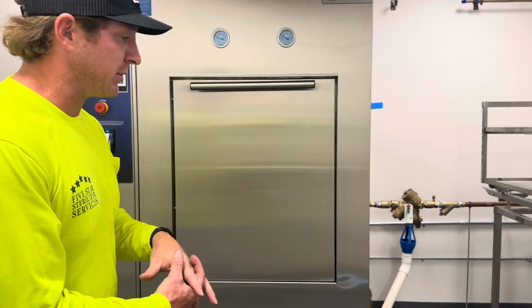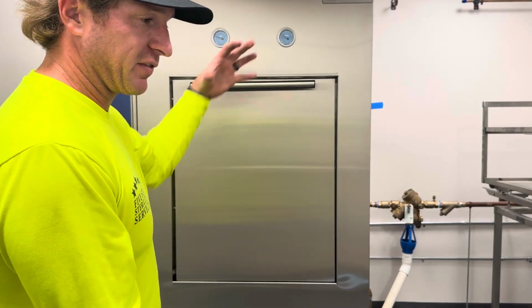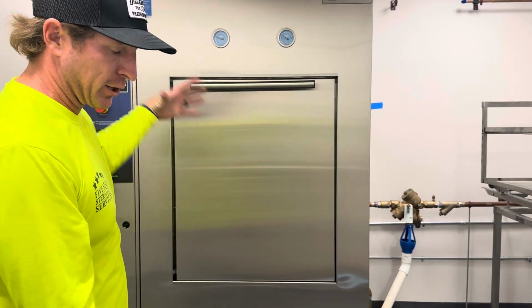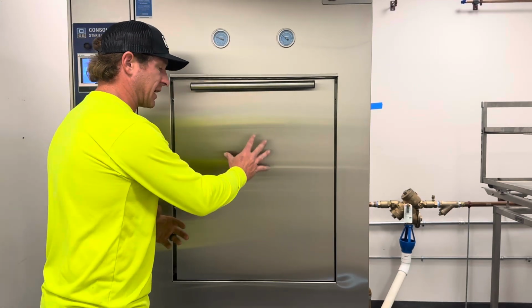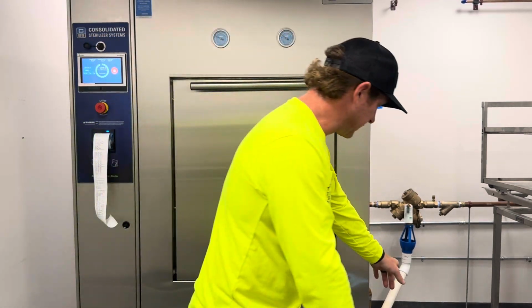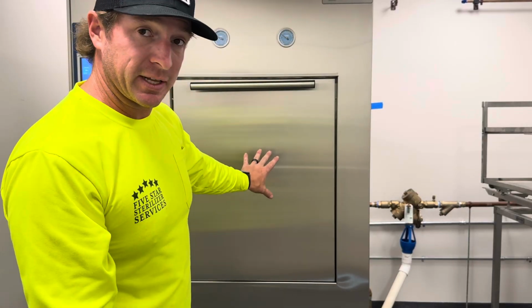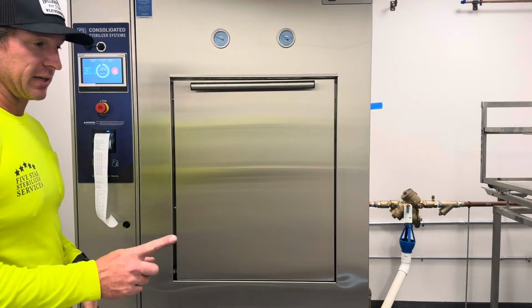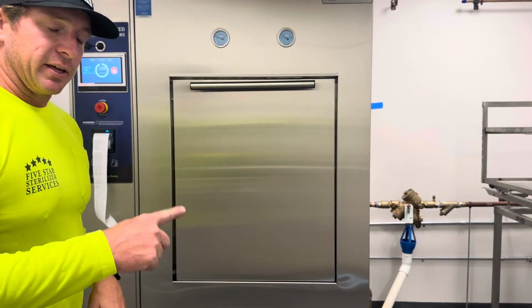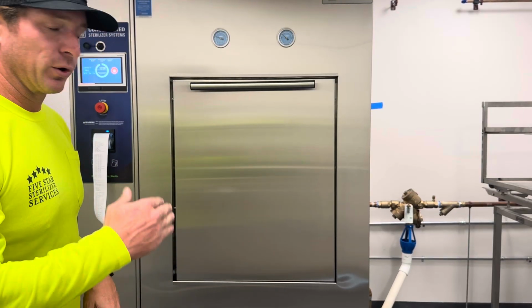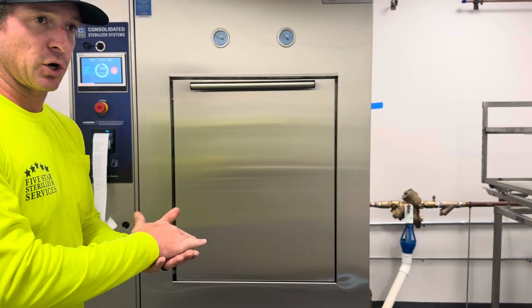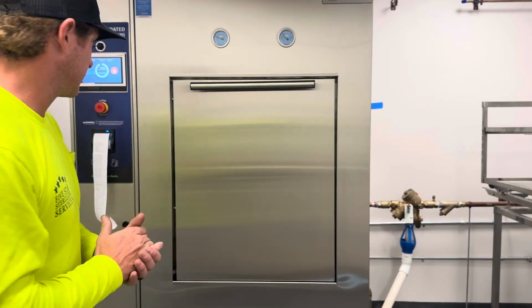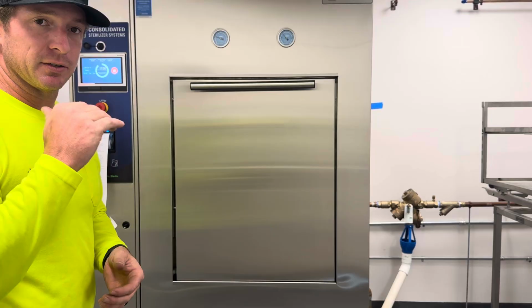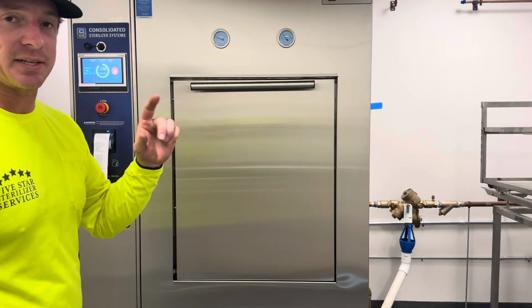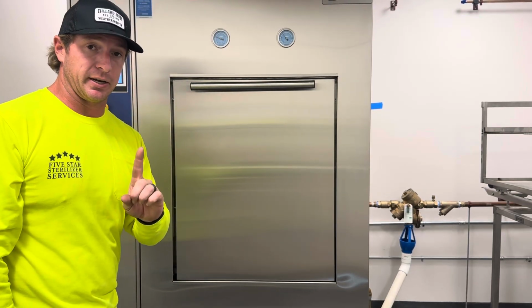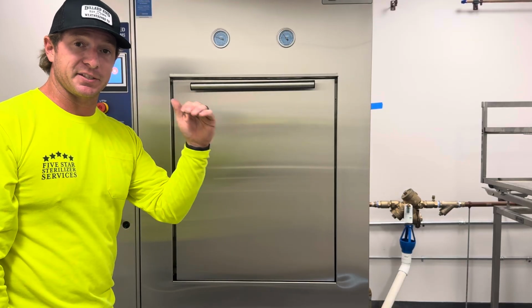We're purging that chamber. So we've opened up the drain valve, we've opened up the steam supply, and we're purging all of the air that we just captured inside there. We're pushing that down the drain where it's nothing but straight steam inside the chamber. That's the first phase. After that, you will either go into your vacuum pulses or you'll go into the charge phase where we're charging up to our target temperature. Once you achieve your target temperature, this machine has a 1-minute stabilization period before it goes into the sterilize phase.